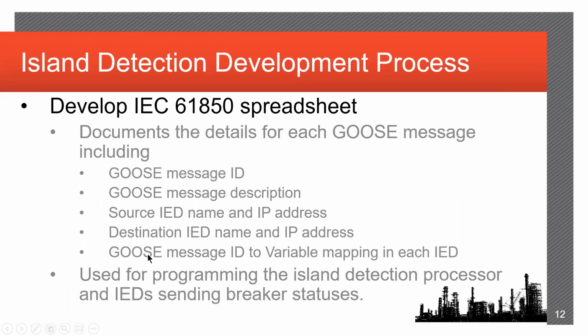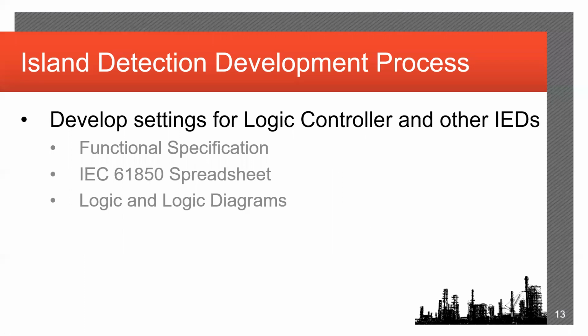So that's what the fifth bullet point, Goose message ID to variable mapping in each IED, actually means. We use this spreadsheet along with the logic diagrams whenever we were actually programming the processor as well as the IEDs themselves. Next step was to actually develop those settings, and of course, the functional specification I said early on, that was the roadmap for all of the engineering that was going to come after that. Then of course the IEC 61850 spreadsheet that details everything about the Goose messaging, and then of course the logic and the logic diagrams.